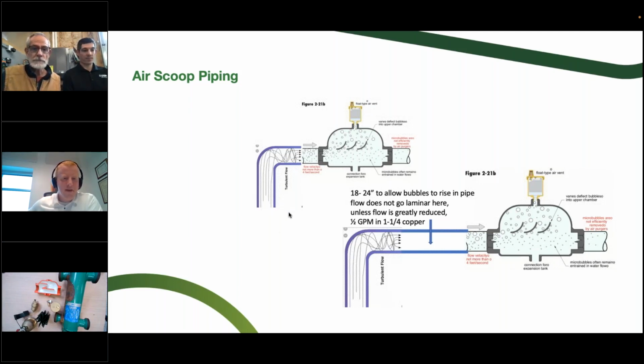Yeah, anytime I typically see these air scoops installed in the field, they're usually not following the rules about the 2 feet of straight pipe beforehand, and it's one of the worst things about the industry, that a lot of times you can have something installed that's not installed as well as it should have been. It's still going to work somewhat, but it's not going to be as effective as it could be. And it's those best practices that separate the good from the great.